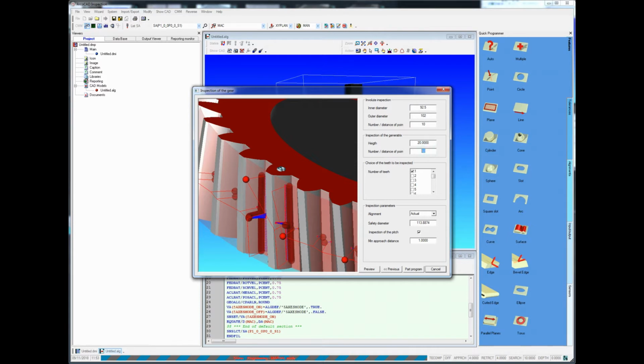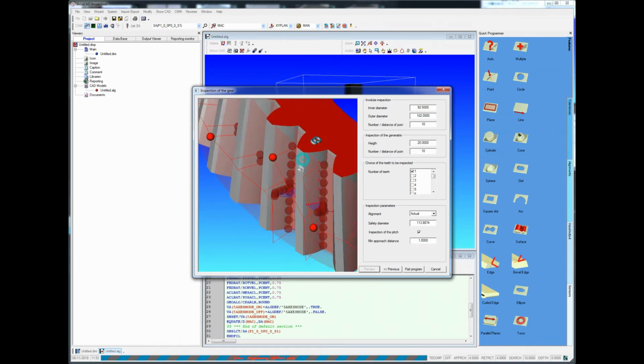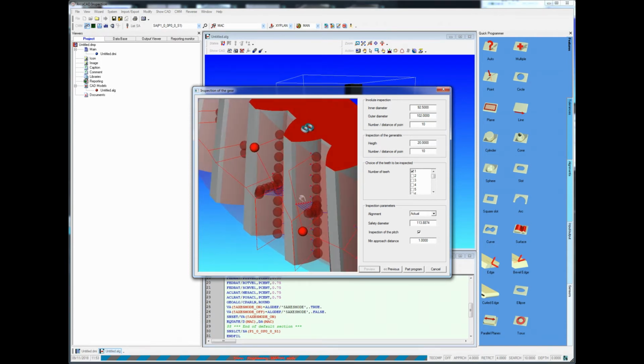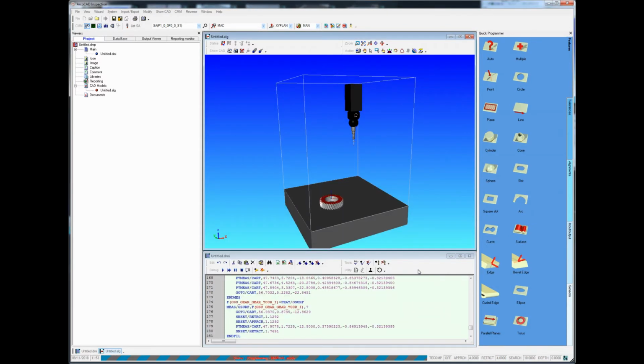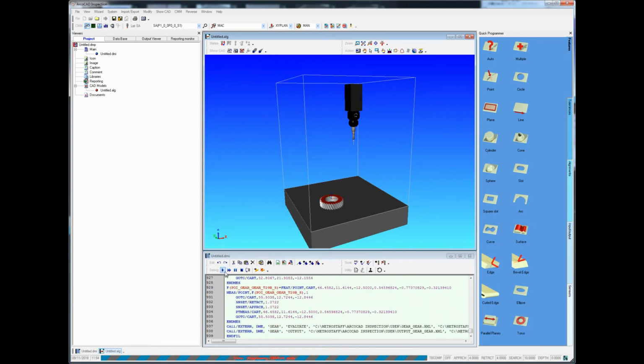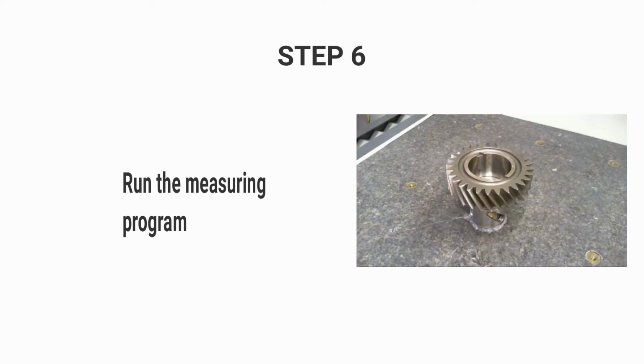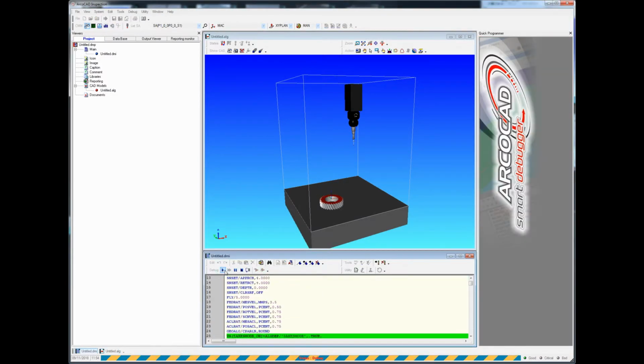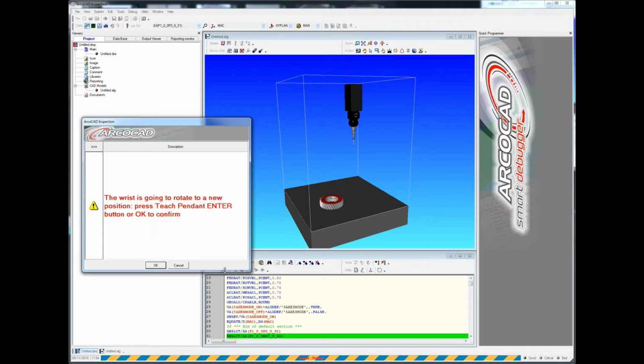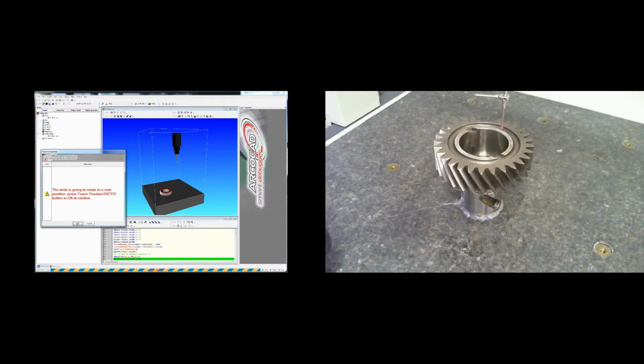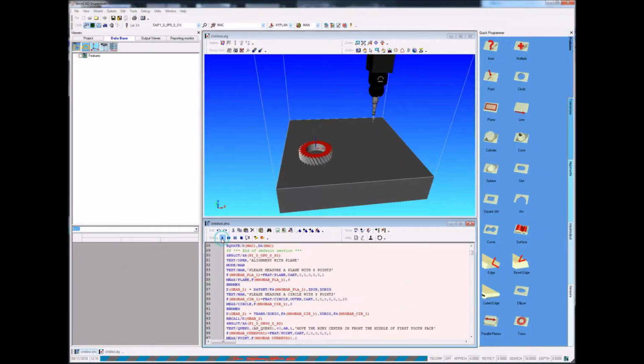in the model. The user can change and preview all the measuring path as well as selecting the required alignment type. The available alignments are cylinder direction and center, plane and circle, 2D synchronization, current alignment as per the customer definition. Once all the choices are made, the full automatic program is generated. The program created by Arco is fully functional, and requires very little expertise to be run. It is just a matter of following the messages to create the manual alignment, and the program will run automatically.